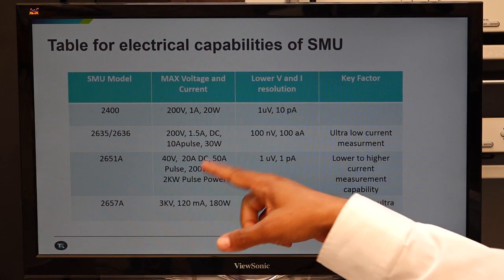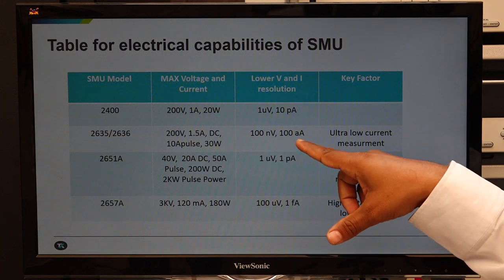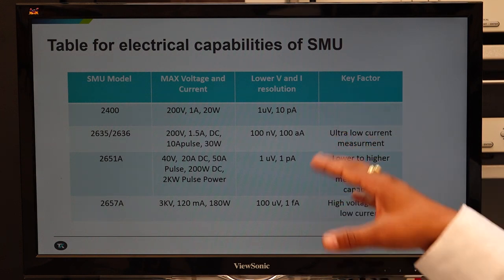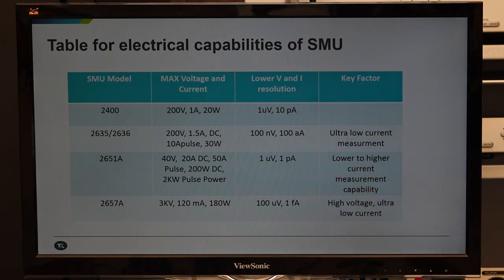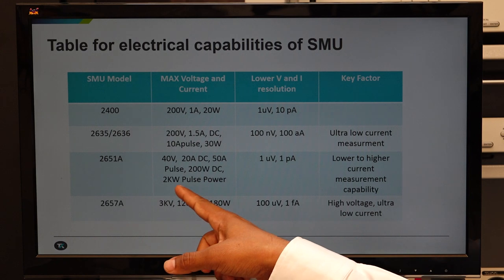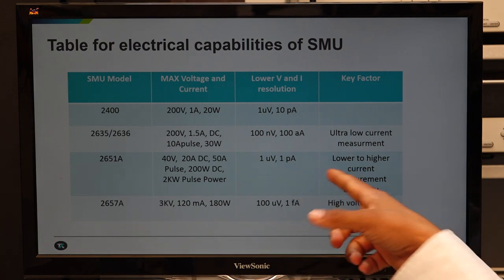The 2635/2636 supports 10 ampere in pulse mode with 30 watt power restriction. On the lower side, it offers 100 nanovolt voltage measurement resolution and 100 attoampere (10⁻¹⁸) current measurement resolution, useful for measuring very low leakage current. SMU 2651 is a high current SMU capable of sourcing 40 volts, 20 ampere DC, and 50 ampere pulse with 200 watt DC power restriction, and can support 2 kilowatt power in pulse mode. On the lower side, it offers 1 microvolt and 1 picoampere resolution.